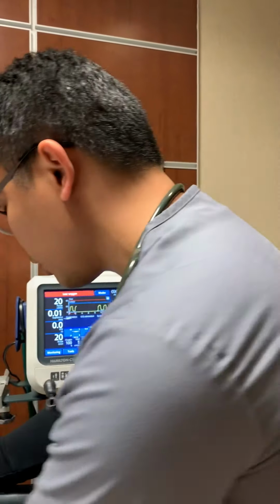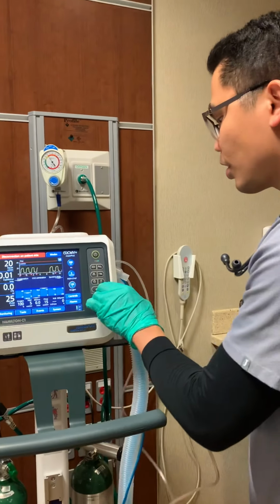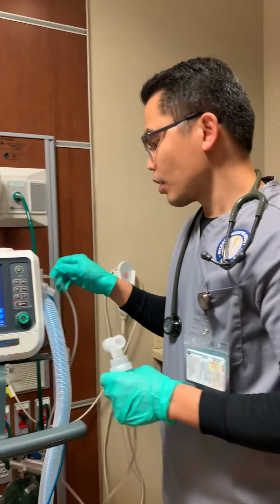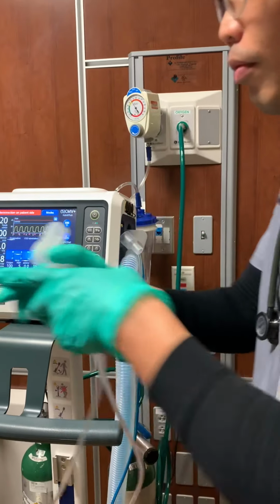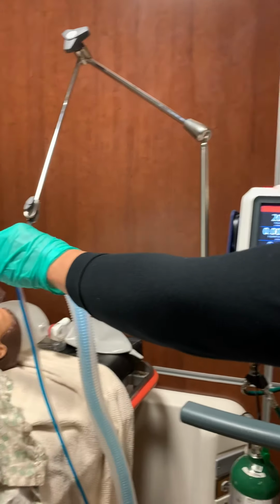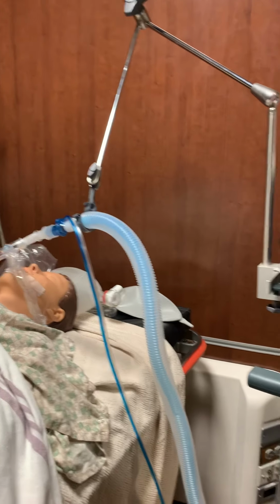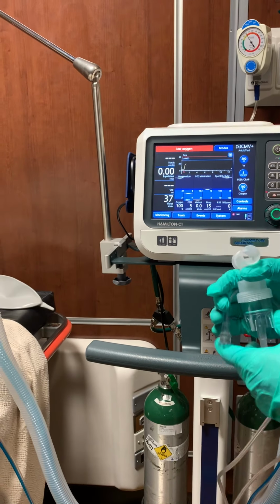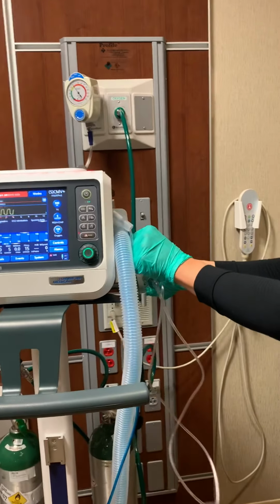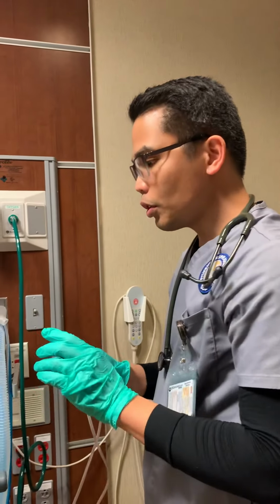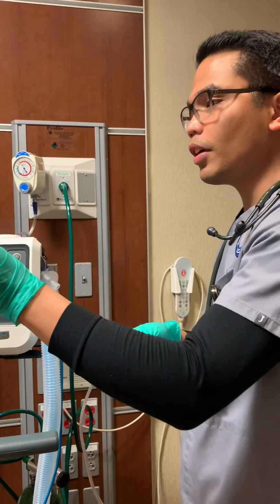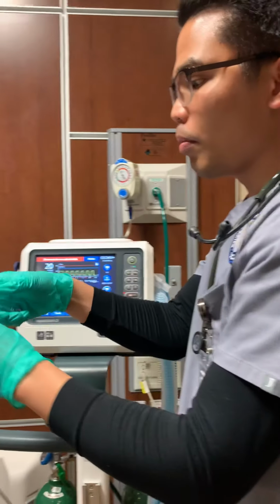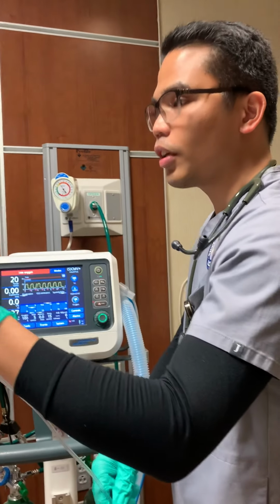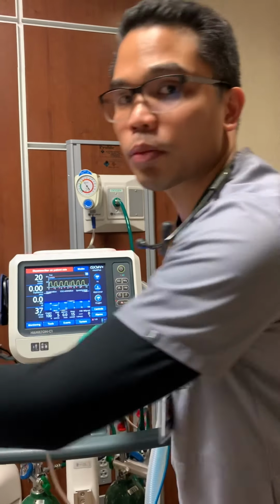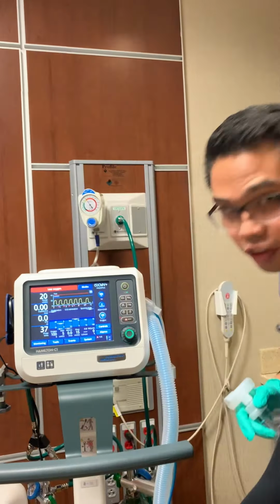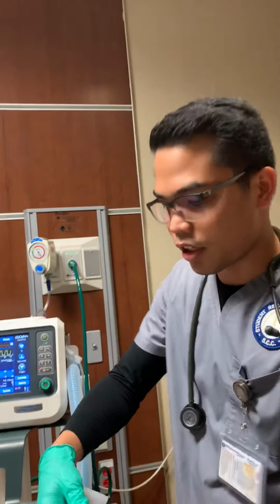And then also another thing to note with the nebulization treatment, because this one is a single limb, some ventilators have a double limb with a Y connector piece. The one has been connected towards the humidifier, that is the inspiratory side, and then the other one is connected on the side, which is on the expiratory side. So usually, if we want to give nebulization treatment with a double limb, make sure we inspect carefully that we hook up the nebulization kit on the inspiratory side. Make sure we inspect it at all times. So that is one of the important things with the nebulization treatment.